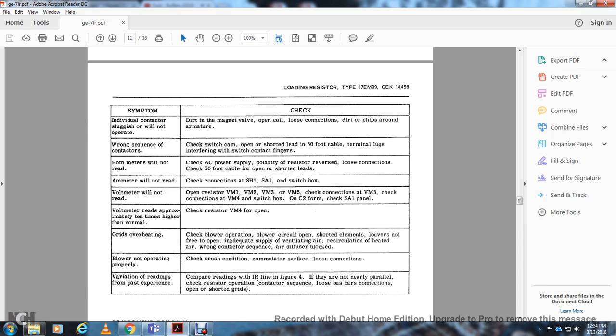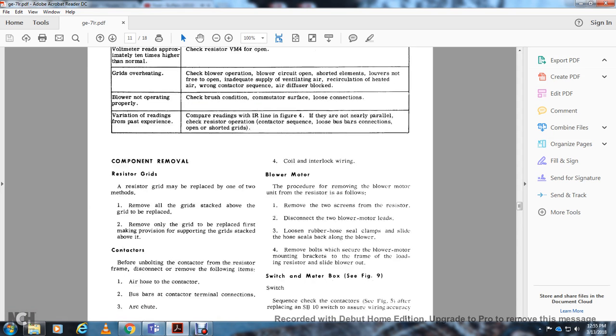Check brush conditions. Commutator surface, loose connections. Variation of the readings from past experience. Compare readings with IR line, figure 4, if not nearly parallel, check the resistor operation, contactor sequence, loose bus bar connections, open or shorted grids.